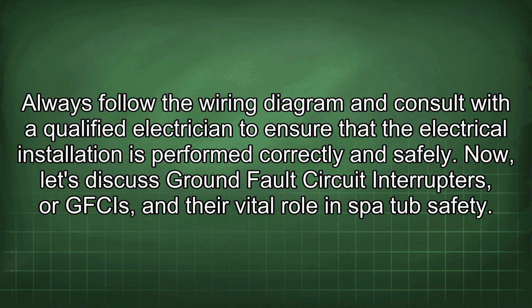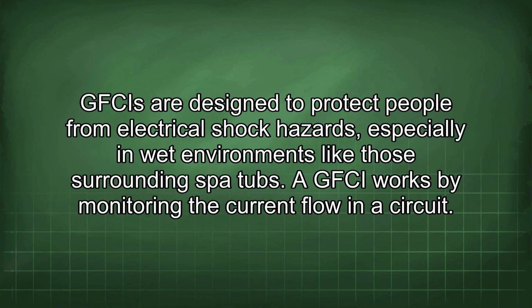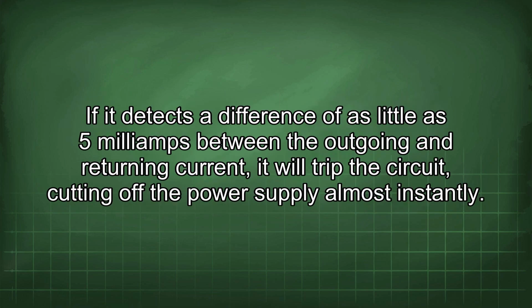Now, let's discuss ground fault circuit interrupters, or GFCIs, and their vital role in spa tub safety. GFCIs are designed to protect people from electrical shock hazards, especially in wet environments like those surrounding spot hubs. A GFCI works by monitoring the current flow in a circuit. If it detects a difference of as little as 5 mA between the outgoing and returning current, it will trip the circuit, cutting off the power supply almost instantly.